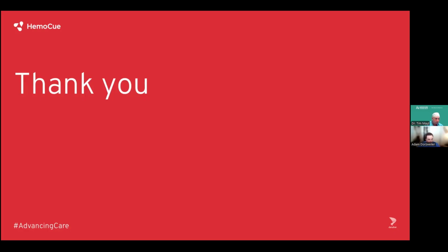All right, it sounds like this next question is a good one. The question is: the surgeons at my hospital really push for smaller arterial cannulas, resulting in higher line pressures. To your knowledge, what's the high positive pressure that can result in hemolysis? The number that's quoted from some very early studies from the 60s was actually done for shear stress, and it was 120 dynes per centimeter squared. That is the shear stress out of an arterial cannula that has a significant impact on hemolysis.